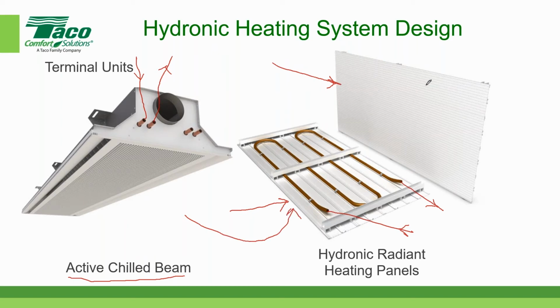And these are designed to blend in with ceiling types. In other words, some manufacturers will actually paint them to look like a ceiling panel, like a 2-foot by 4-foot ceiling panel, or a 2-foot by 6-foot. 2x4 is probably the most common size. I've designed lots of systems using these hydronic radiant heating panels. They're quite popular in the Northeast.